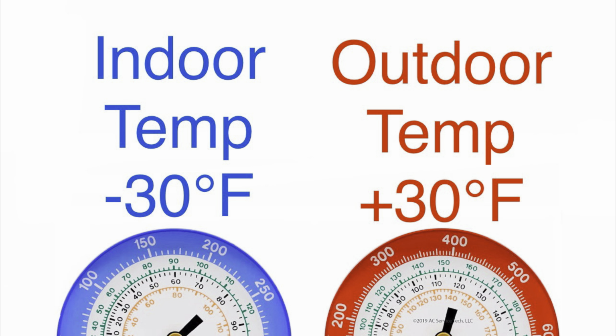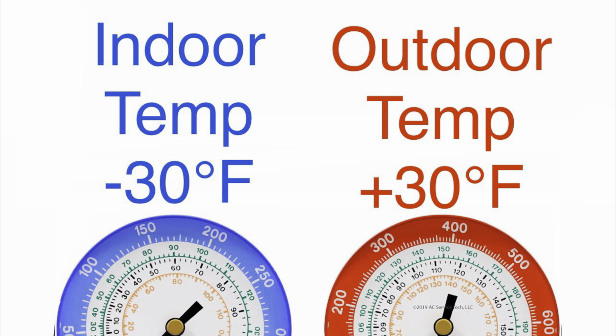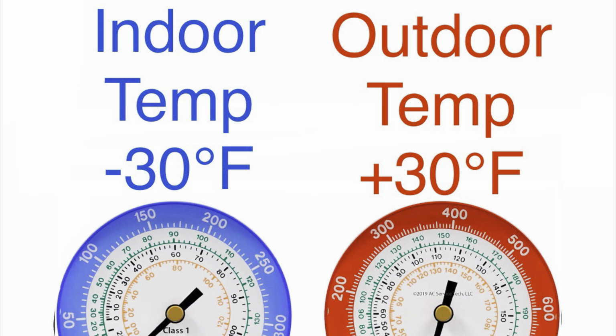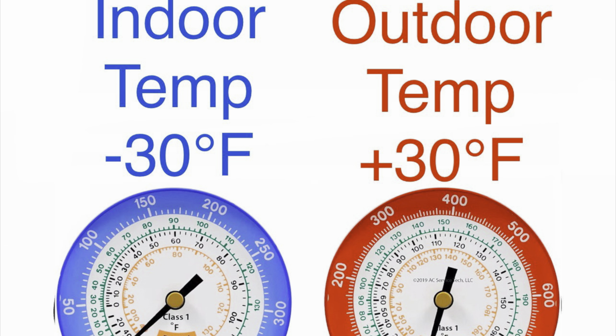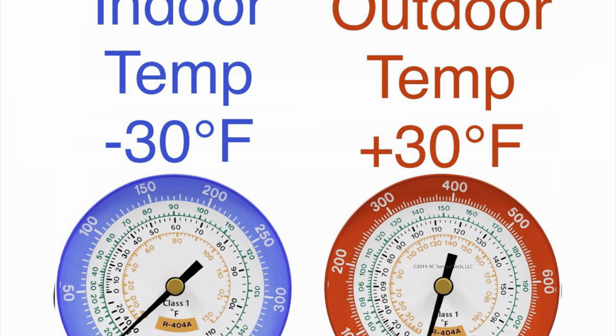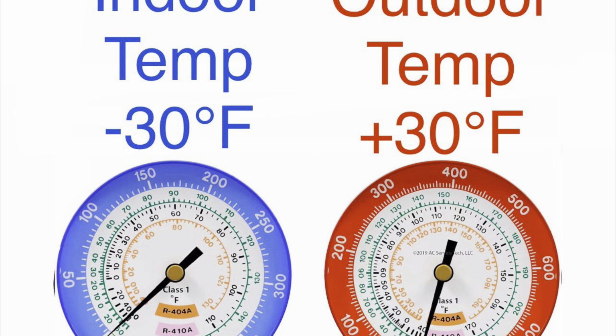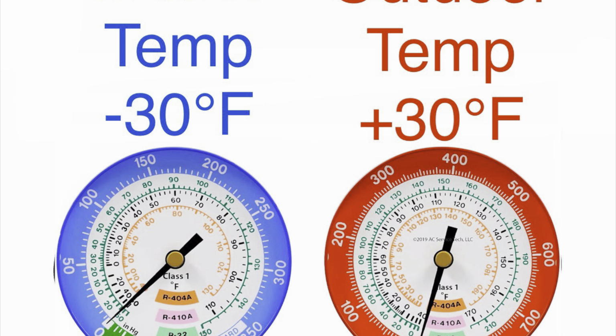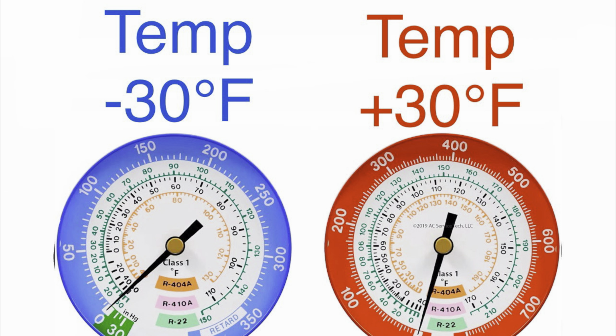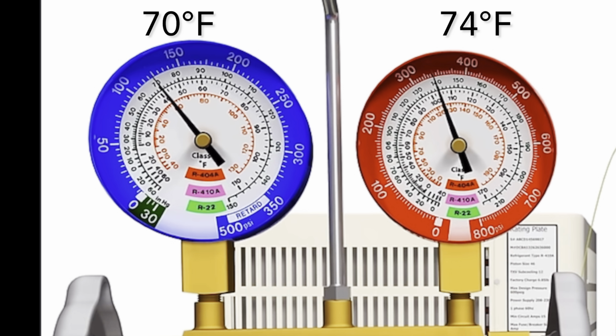These characteristics of the refrigerant are applied to our pressures and temperatures on the gauges. So we take the indoor temperature and subtract 30 degrees from it, and that is our target temperature for the low side, and we take our outdoor temperature, add 30 degrees to that, and that's our target temperature for the high side. Here are pressures that will resemble actual real life scenarios.